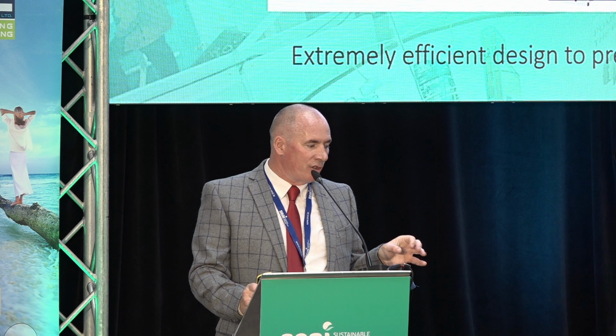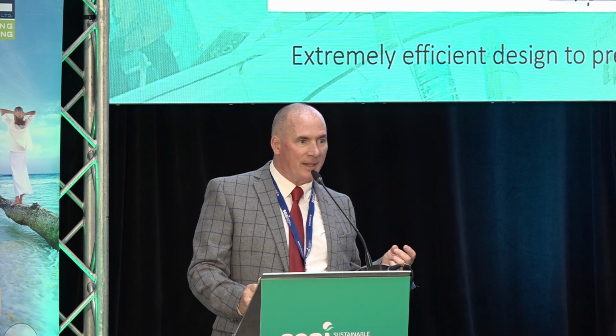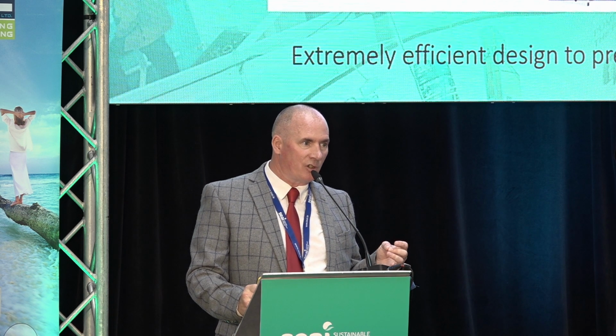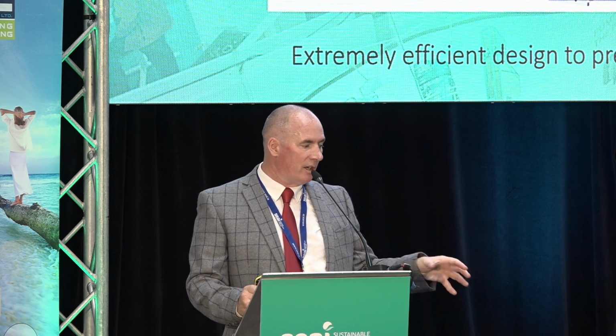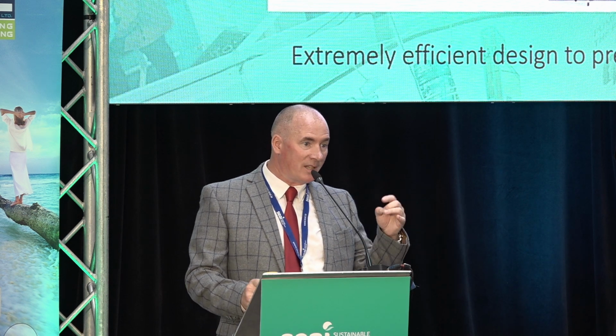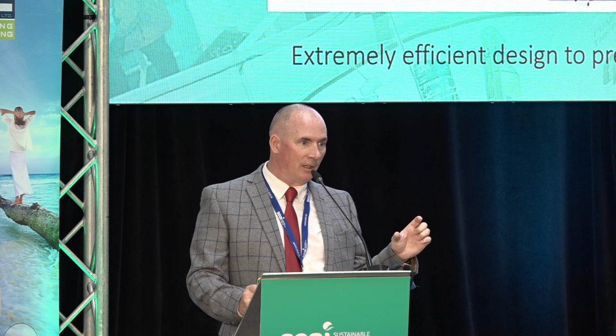There is a third, extremely efficient method of preheating your domestic hot water, pretty much 2/3 for free. ERMEC have done extensive studies with the University of Padua, and they've discovered how we can utilize the free energy from a multifunctional heat pump when it's in chiller mode, and we can preheat our domestic hot water, typically about 2/3, and then we can use a water-to-water booster for the final third.